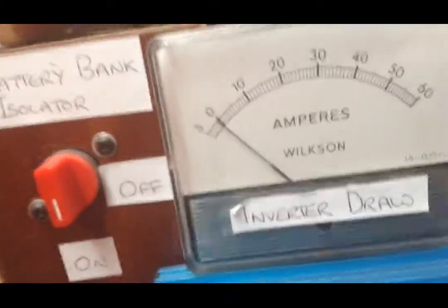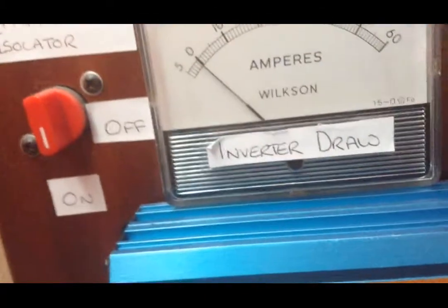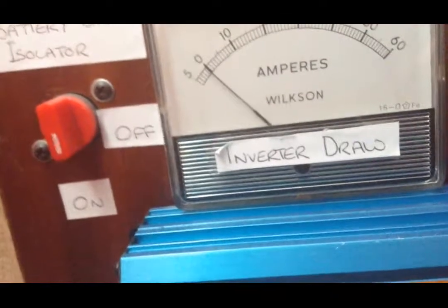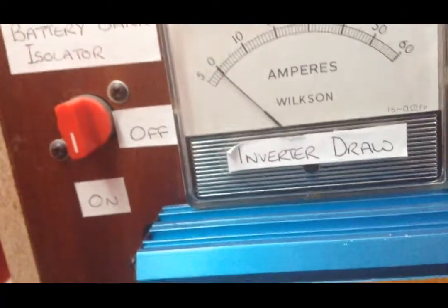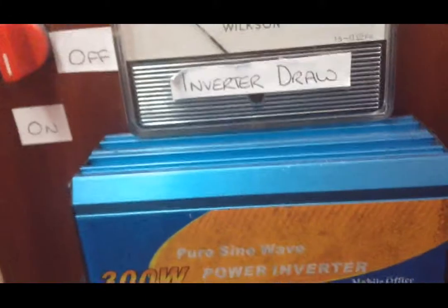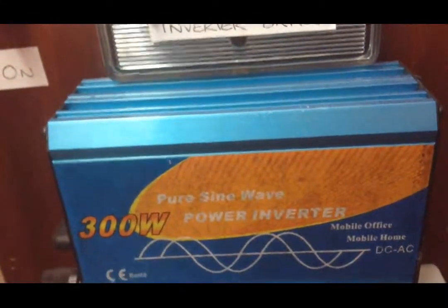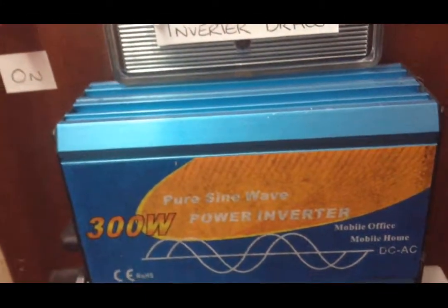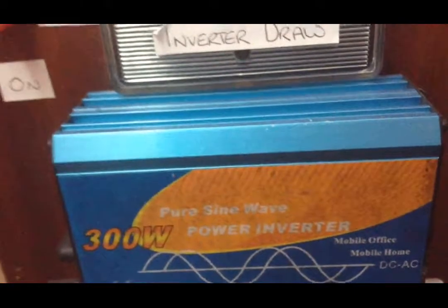Also, all the wiring between the meter and the breaker and the inverter needs to be thick enough to carry the maximum load current of the inverter. So that's something to bear in mind.